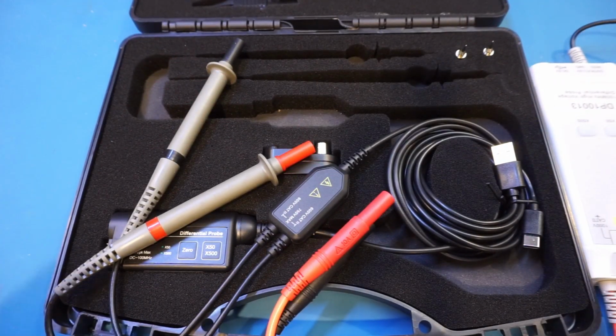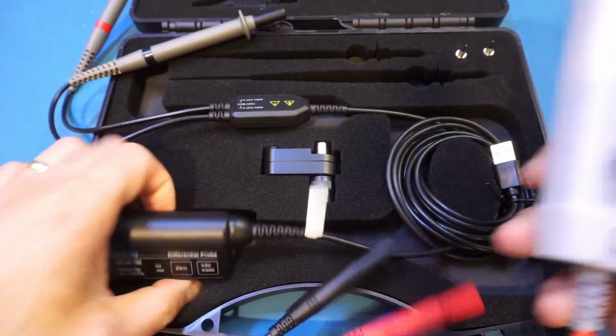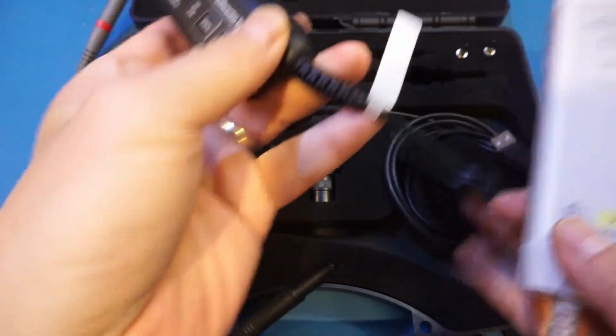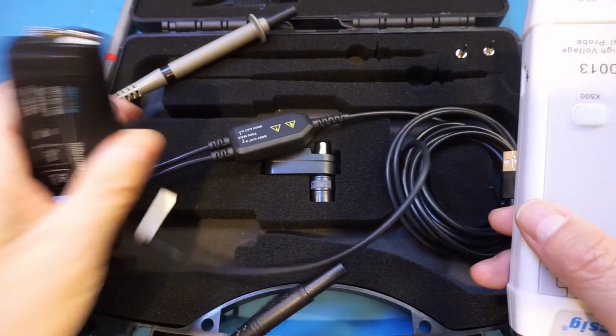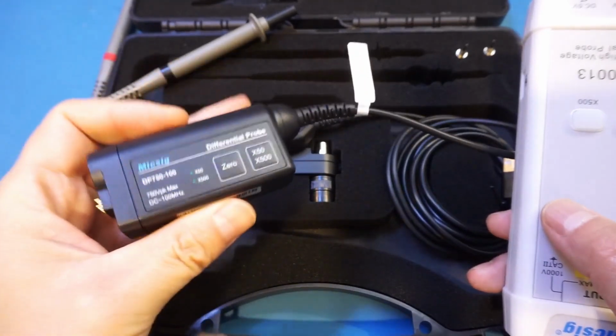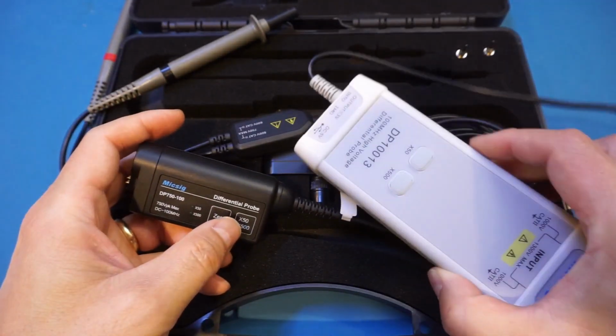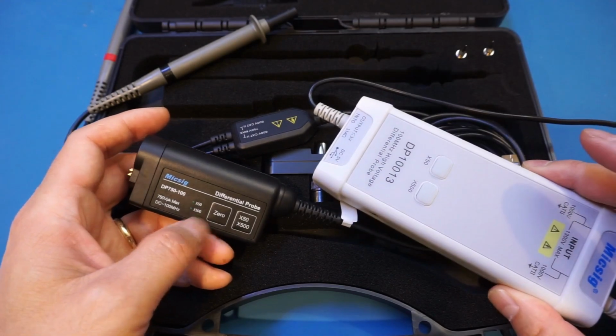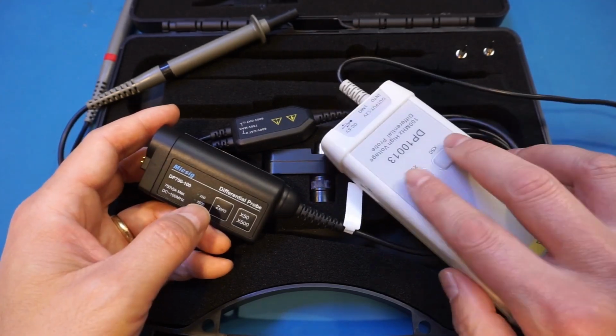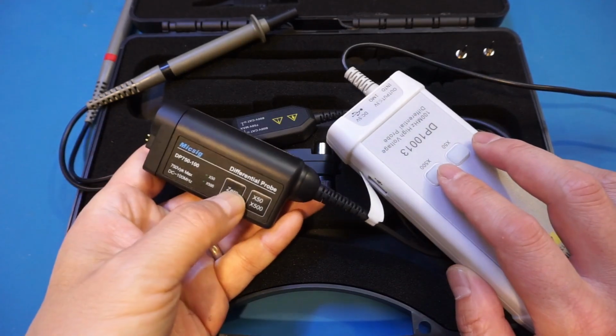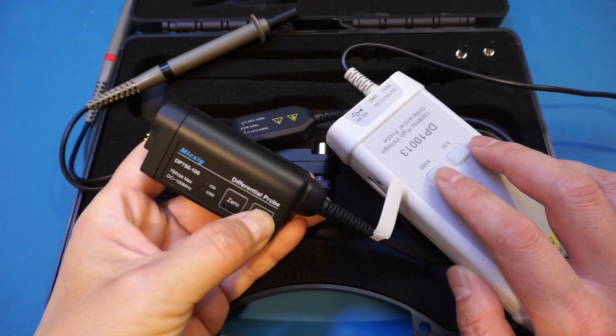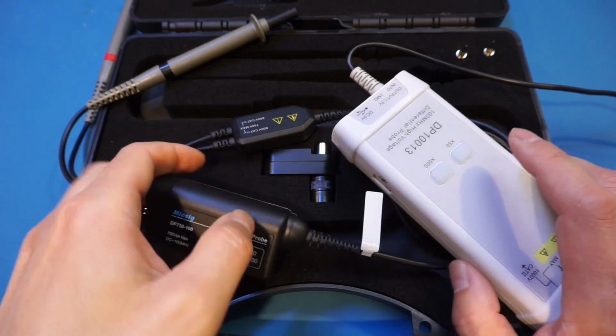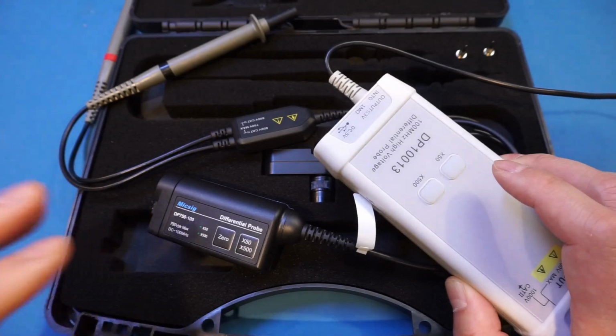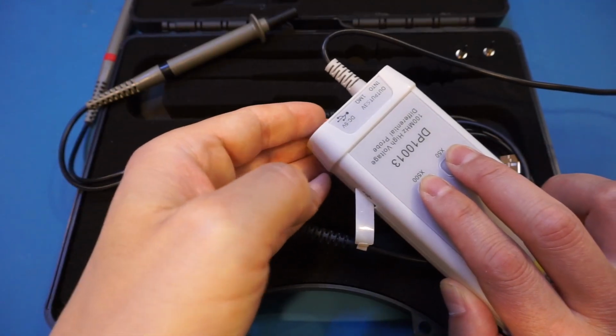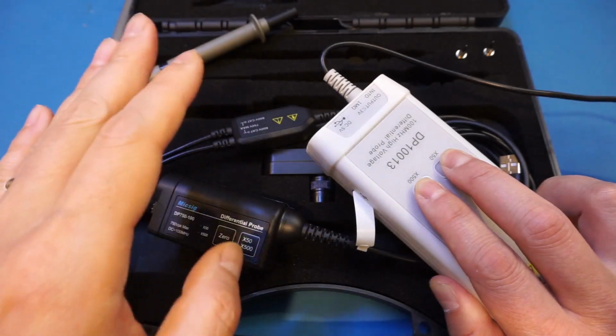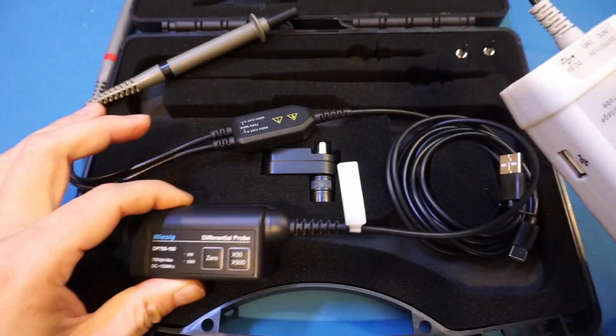Now, while we have both of these probes out, I just want to quickly show you them side by side, and you can see that this new DP750 is definitely more streamlined, as everything is enclosed within the head of the connector here, whereas you do have this box for the DP10013. Now, the buttons are slightly different. This one has two physical buttons, whereas the DP10013 has one additional button, because the range is done in this one button here. For the DP10013, we do have a zero function. We can press these two buttons simultaneously while plugging in your power, and that's how you do the zero calibration. So that's just the slight difference here.